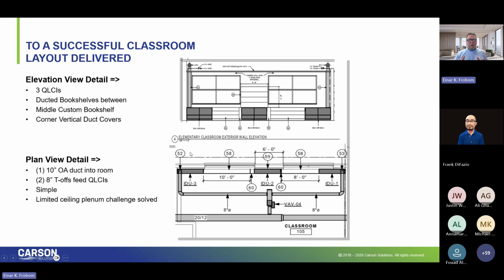And so in these renovations, the biggest hurdle is how do you get the outside air to these spaces? But it's worth fighting for. But go back to the system. This is a DOAS-based system that's bringing in code minimum OA only, 350 to 400 CFM. So in a lot of these classrooms, we've got 14 inches between the drop ceiling and the roof line.